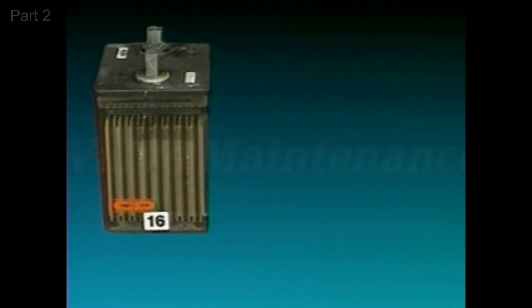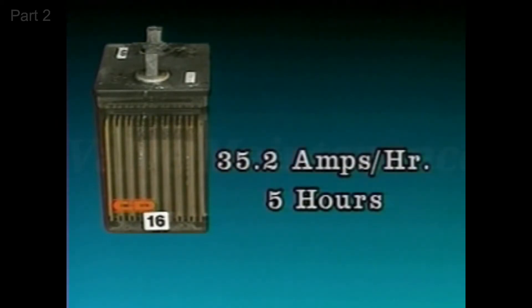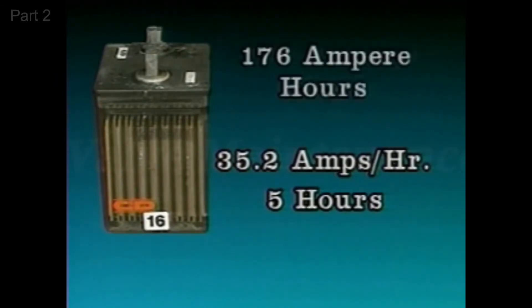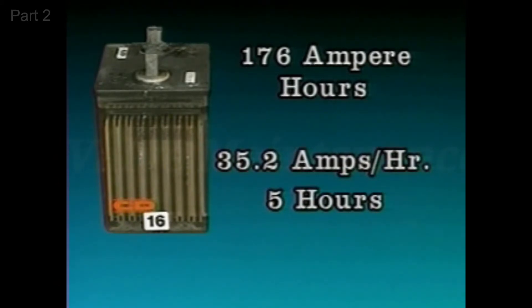The capacity of a cell changes with different current demands. For example, if the load demands 35.2 amps from this cell, the cell will be able to provide 35.2 amps for only 5 hours. This translates into an ampere hour rating of 176. So the cell capacity, or ampere hour rating, is lower at higher discharge currents.